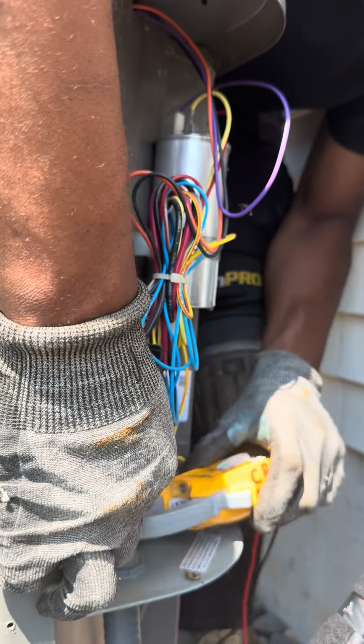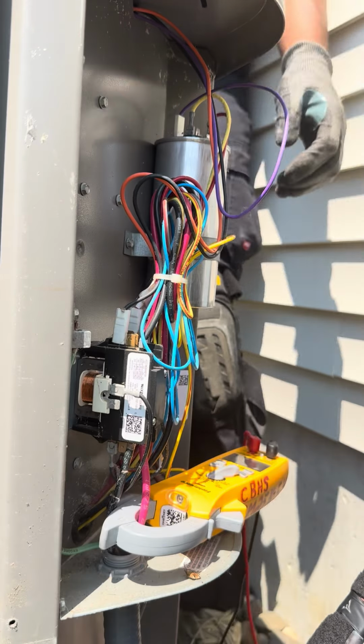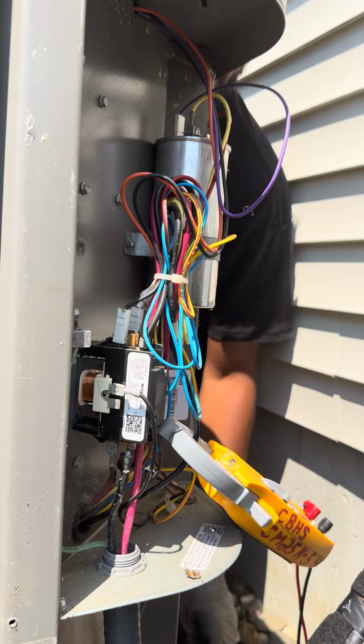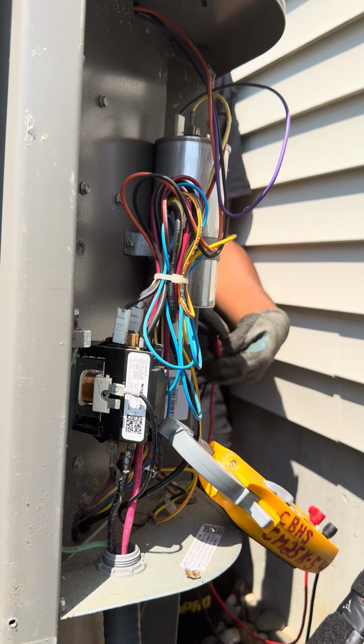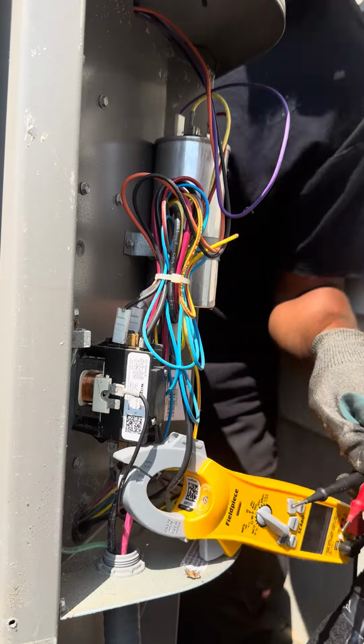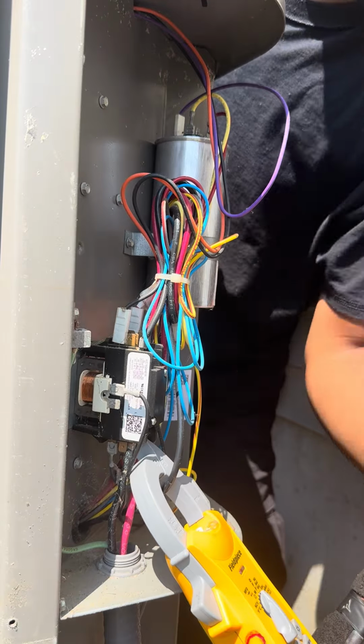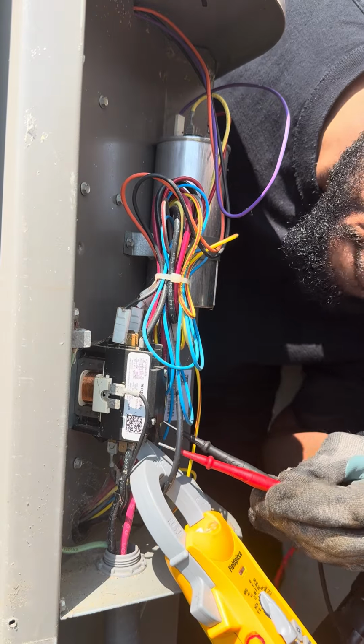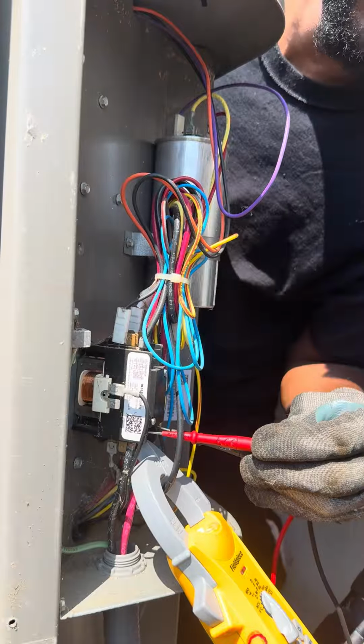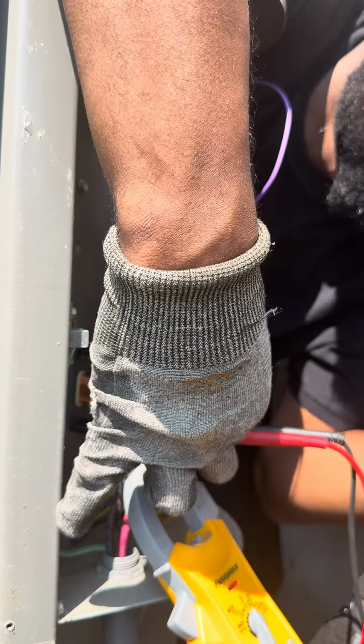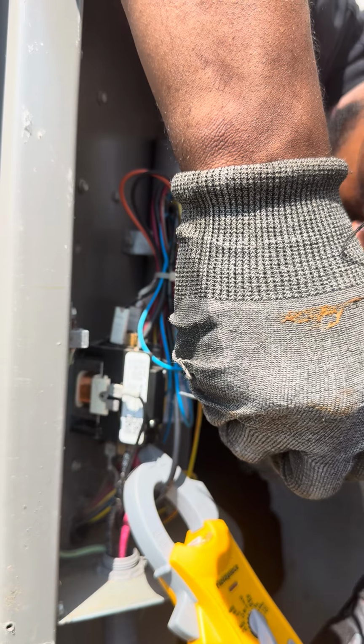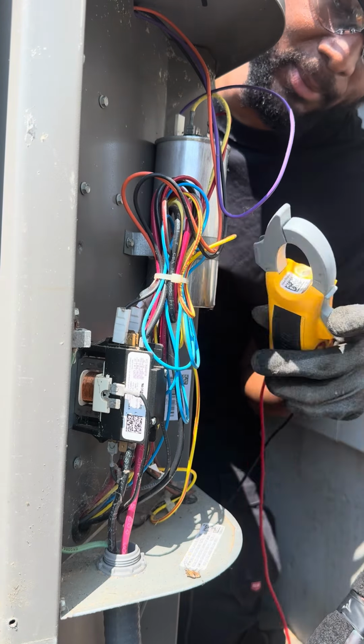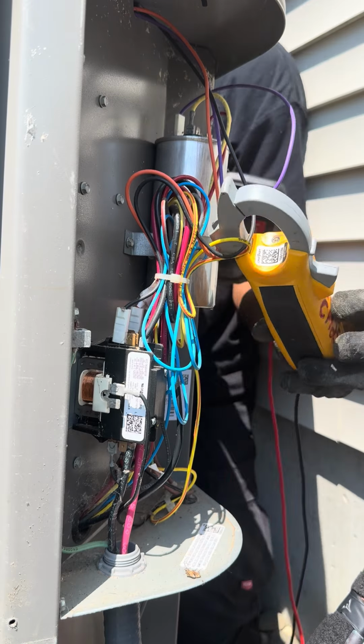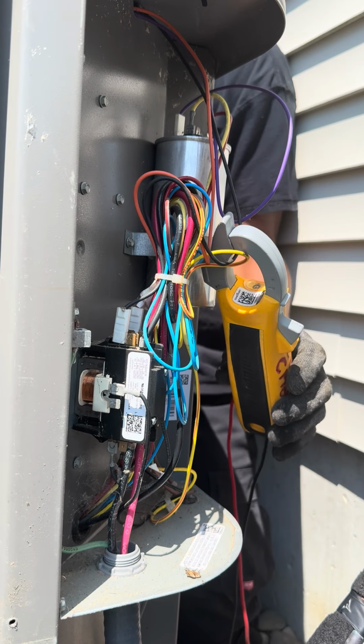The overall amperage to the whole system, to the condenser, then checking the amperage to the compressor, and then going to check the amperage to the fan. Just making sure everything is good according to the data plate, going over my contactor, then checking the capacitor afterwards, and eventually I'll turn it off.